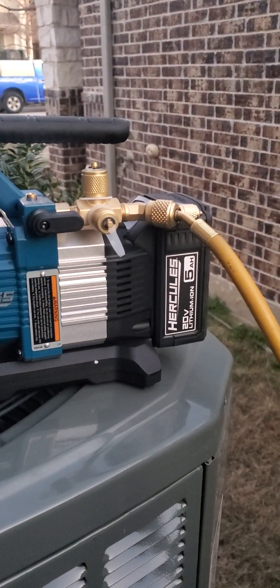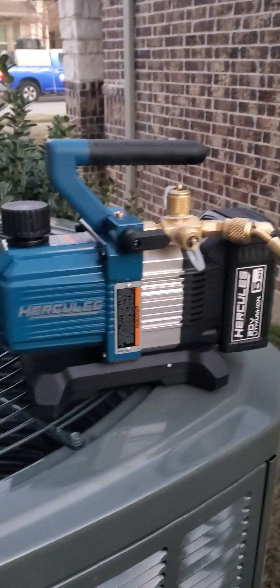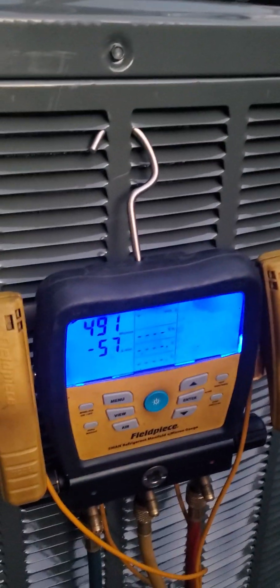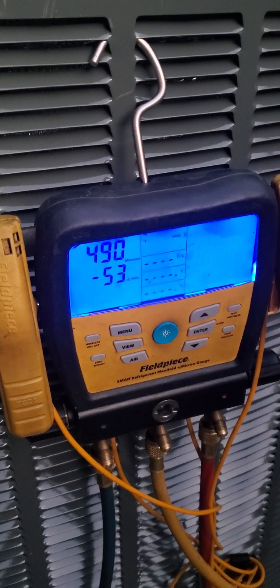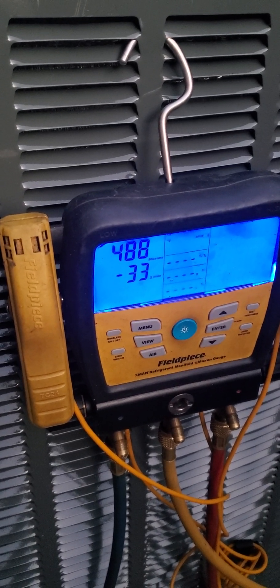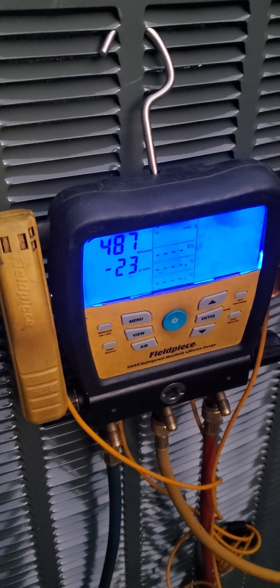Harbor Freight 20-volt vacuum pump — below 500 microns and still pulling down. It's been on for about 30 minutes. This is a brand new 5-ton Trane, so it's a big system with big lines and a big evaporator coil.